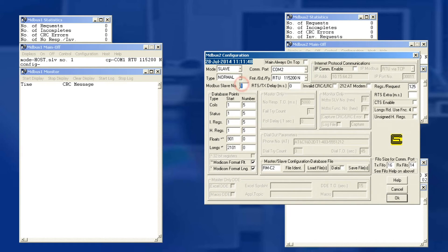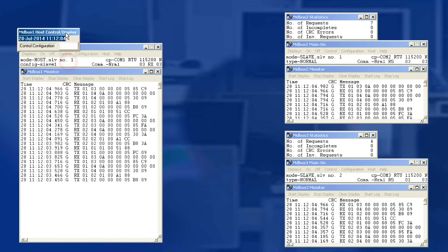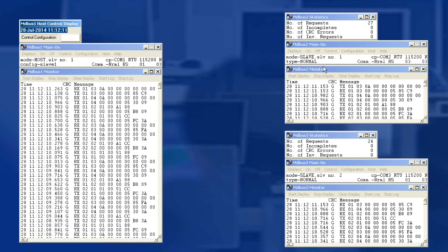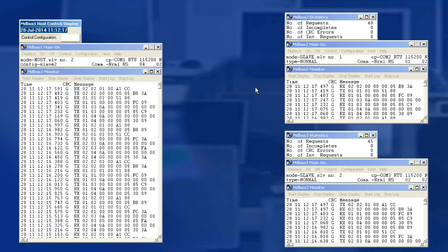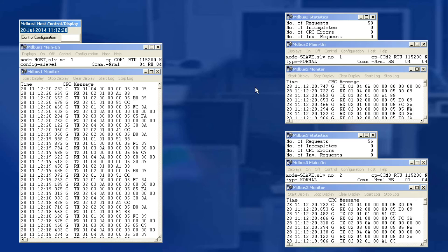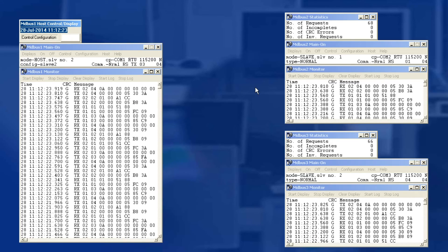Now that we've proven functionality, I want to get some real data flowing. Using MDBus, which is a Modbus protocol polling tool, I have the master and two serial slave RTU devices. The master poller will be requesting analog and digital registers from each RTU. Each RTU has a different slave ID, so it will only respond back with the data when the message is sent for that unit. As I start the master, notice how it cycles through the two different slave IDs. Because the Orbits are in multipoint mode, each RTU receives all messages but only responds back when it's their slave ID. UDP multipoint mode ultimately allows serial-to-serial polling over an entire system using one multicast IP address.